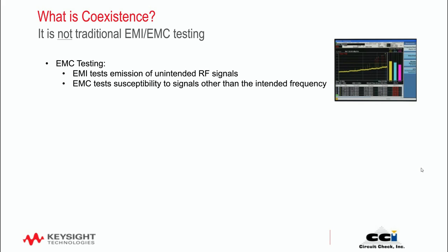EMC, electromagnetic compatibility, then tests the susceptibility of a device to some signal other than the intended frequency. So your device may be operating at 900 megahertz or 2.4 gigahertz, and this tests to see whether your device is upset due to strong signals on some other frequency. It doesn't specifically look at the communications frequency of a wireless device.